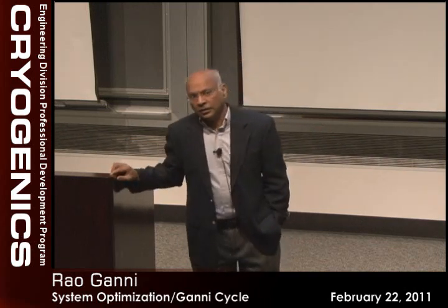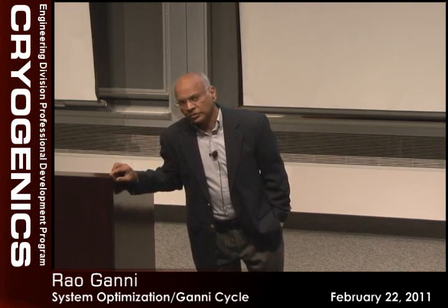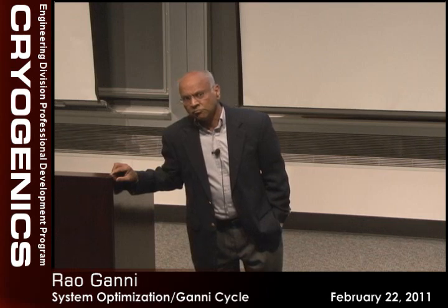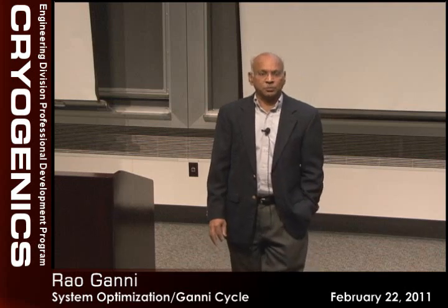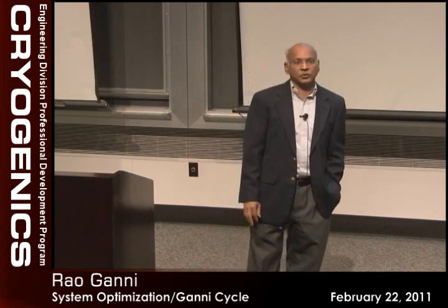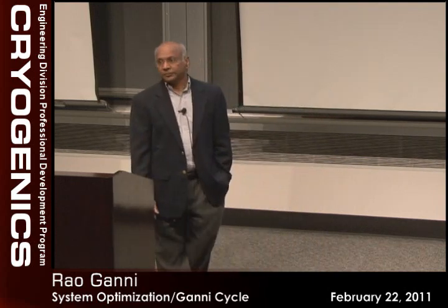Related to this class then, does the discharge pressure variation affect the liquid nitrogen usage for our plants? No. Liquid nitrogen is independent of the pressure. It basically depends on the mass flow going through the system, and the mode: liquefier or refrigerator.